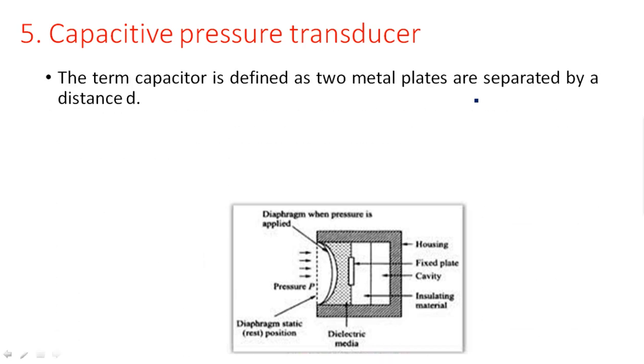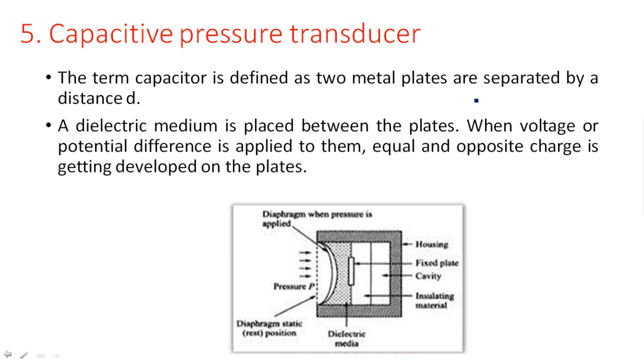Coming to the last type: capacitor pressure measurement. A capacitor is defined as metal plates separated by a distance d, with a dielectric medium placed between the plates. When voltage is applied, equal and opposite charges develop on the plates. The basic formula is C = εA/d, where ε is permittivity (ε_r × ε_0), A is area of the plate, and d is the distance between the plates.